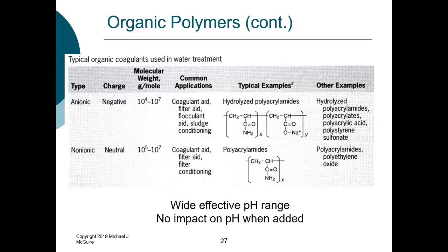So during the entire time they were operating and treating Flint River water, they kept changing the concentrations of the anionic and cationic polymers. It's one of the few places where I have ever seen anionic and cationic polymers both added. But as I've said multiple times when I talk about Flint, essentially what they did was operate a pilot plant at about 15 to 20 million gallons per day, because they were struggling the entire time to maintain efficient operation.